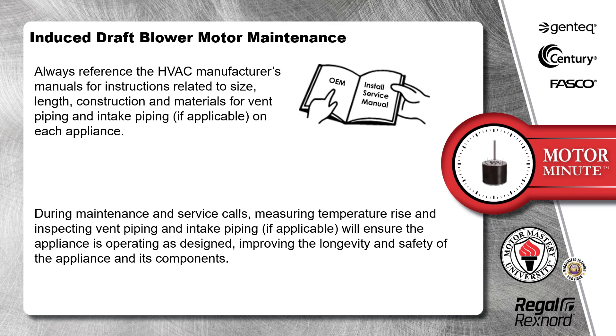During maintenance and service calls, measuring temperature rise and inspecting vent piping and intake piping, if applicable, will ensure the appliance is operating as designed, improving the longevity and safety of the appliance and its components.